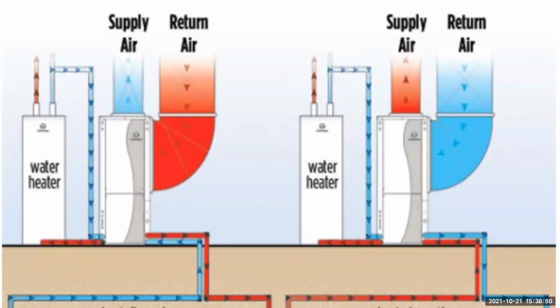So the main difference between residential geothermal and your traditional air source is the fact that the geos, where they get their name, use the energy from outdoors. You remove and you extract, and that's the same as remove. Sorry about that. You put heat into the ground and you remove heat out of it. Usually the ground stays around 45 to 60 degrees. The geotechnology takes the heat in the cold weather months and puts heat back into the ground during the warm weather months. So after you're running your geo unit for a couple years, it really runs more efficient than what it did for the first time.